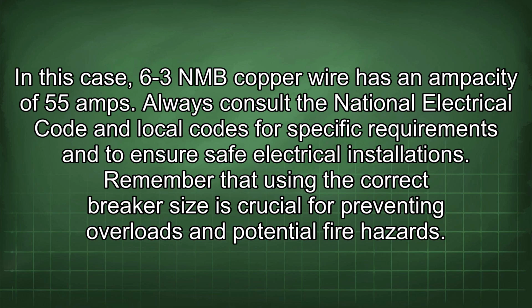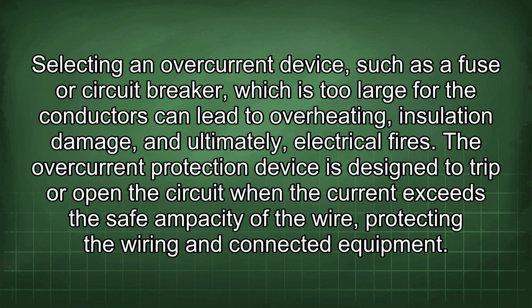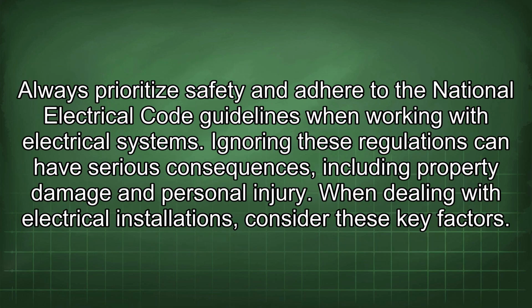Always consult the National Electrical Code and local codes for specific requirements and to ensure safe electrical installations. Remember that using the correct breaker size is crucial for preventing overloads and potential fire hazards. Selecting an overcurrent device, such as a fuse or circuit breaker, which is too large for the conductors can lead to overheating, insulation damage, and ultimately, electrical fires. The overcurrent protection device is designed to trip or open the circuit when the current exceeds the safe ampacity of the wire, protecting the wiring and connected equipment. Always prioritize safety and adhere to the National Electrical Code guidelines when working with electrical systems. Ignoring these regulations can have serious consequences, including property damage and personal injury.